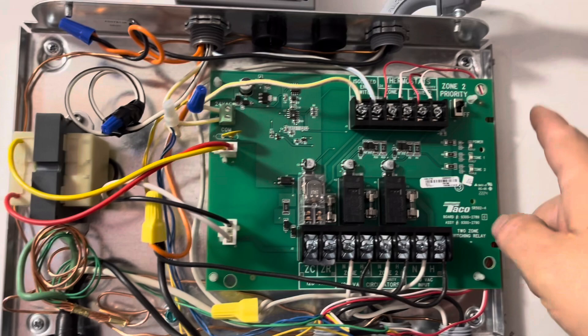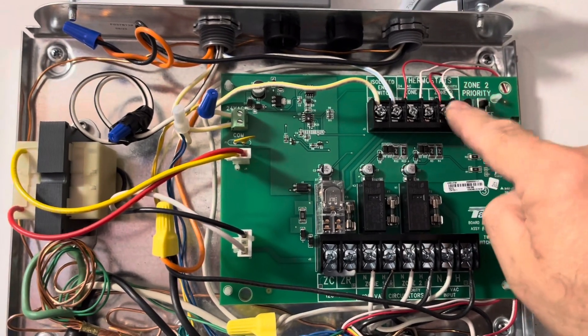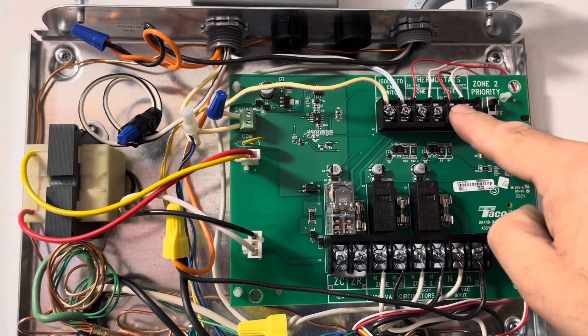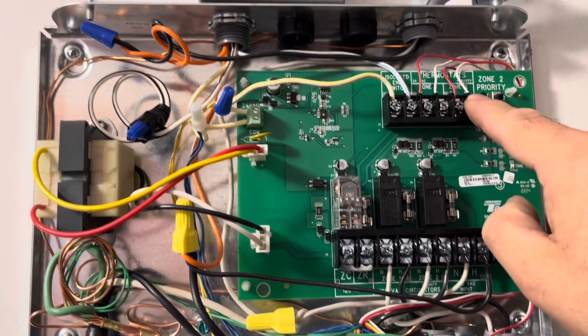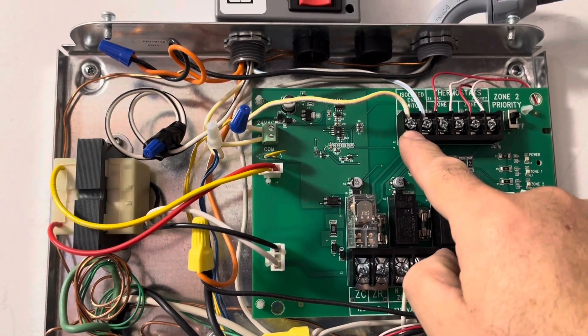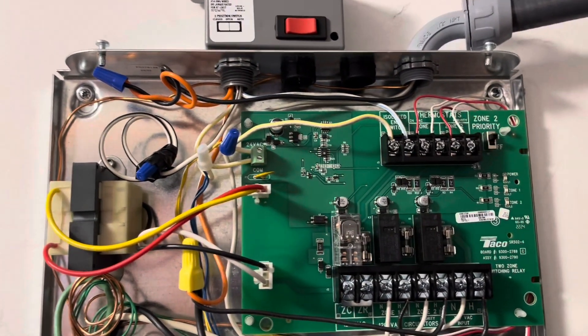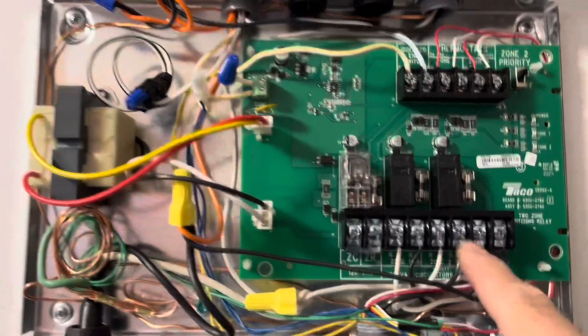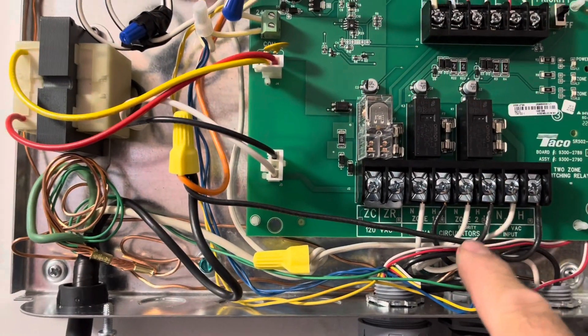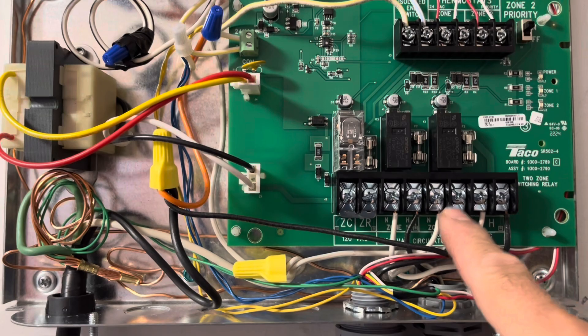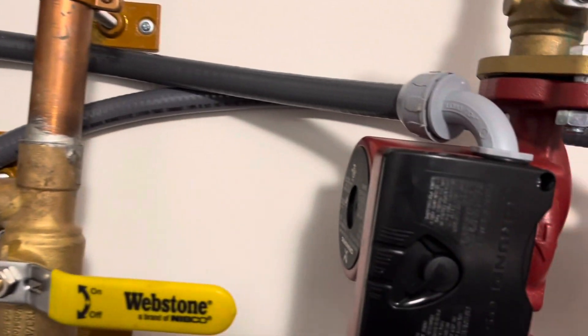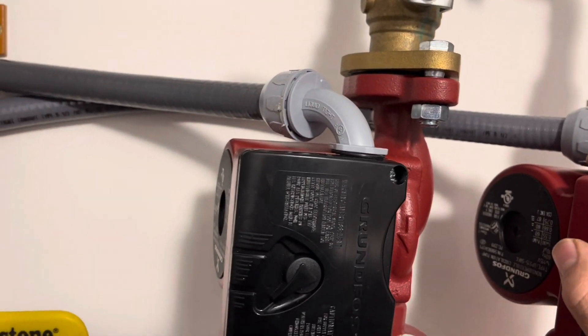So when zone two calls for heat, says 'Hey, I need heat,' this switch closes here. So the primary gets power and then the zone two here becomes energized, which feeds into here, which feeds to my zone two pump.